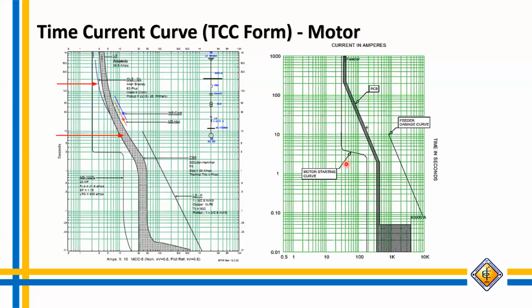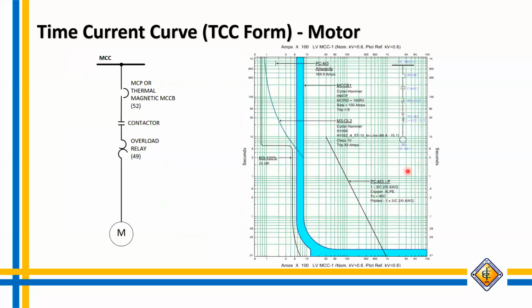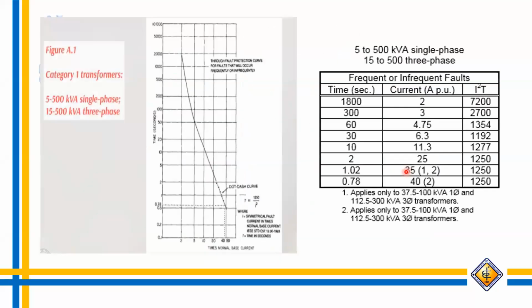So this one is a sample of a TCC using ETAP. I'll just show it later. For transformer damage curves, we have 4 categories. I know those who have taken the TTR here are very familiar with the categories of transformer. So if your transformer is sized 5 to 500 kVA single phase and or 15 to 500 kVA three phase, this is a category 1 transformer. You can use this table in determining the damage curve of your transformer.